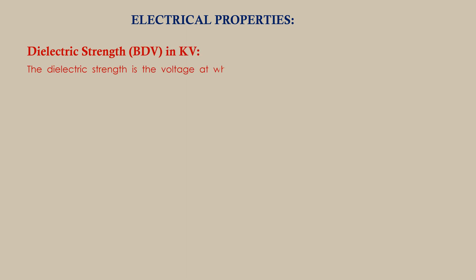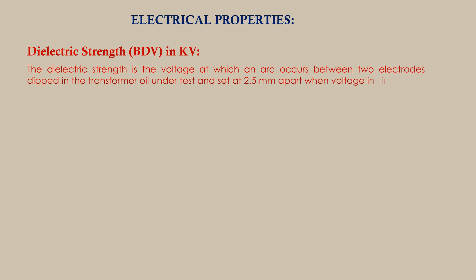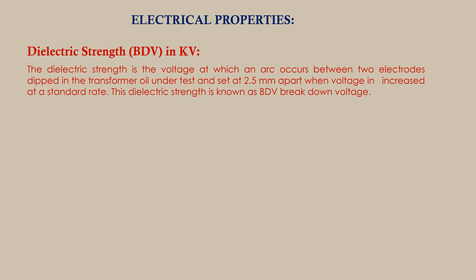Electrical properties — Dielectric strength BDV in kV: the dielectric strength is the voltage at which an arc occurs between two electrodes dipped in the transformer oil under test and set 2.5 mm apart, when voltage is increased at a standard rate. The dielectric strength is known as BDV, or breakdown voltage. Dry and clean transformer oil gives a higher BDV.